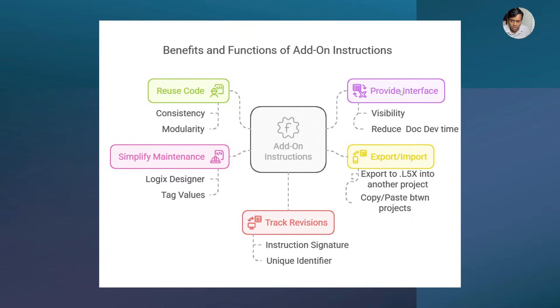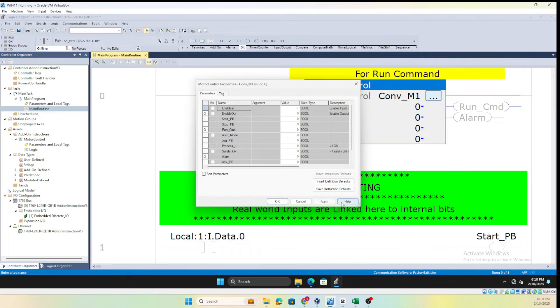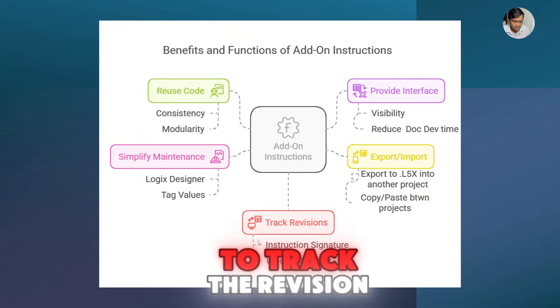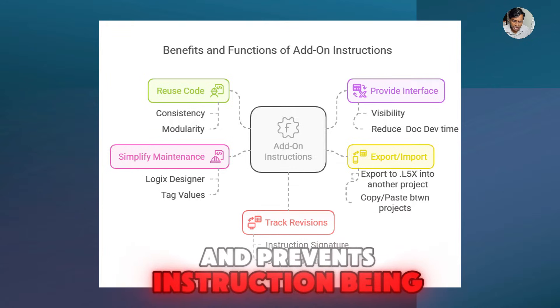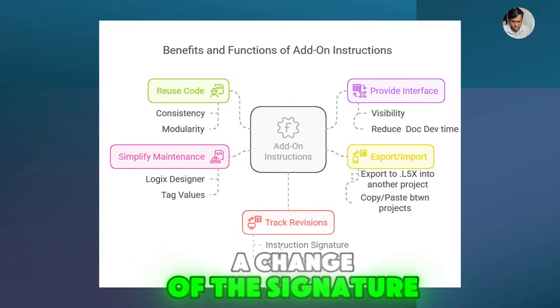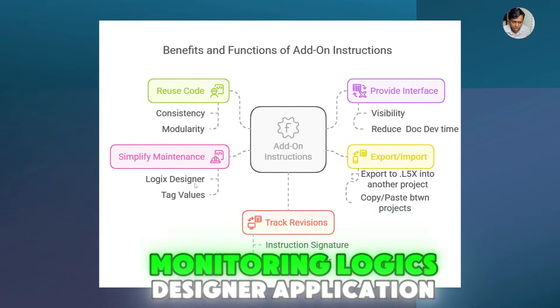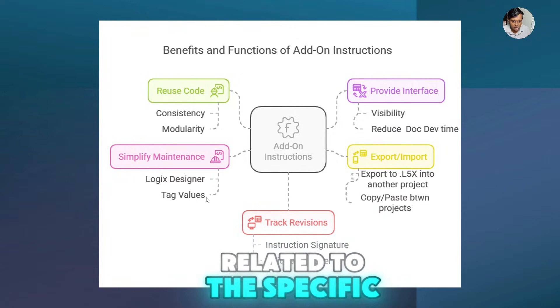Add-on instruction sets also provide an easy-to-use interface just like any other instruction, giving visibility into what's happening and the ability to document how the instruction works. This reduces documentation development time. Another advantage is the ability to import and export into another project using the .L5X extension, or copy-paste between projects. You can also track revisions by adding an instruction signature, which generates a unique identifier and prevents editing without a signature change. Maintenance is also simplified, since add-on instruction sets can be monitored in Logix Designer and will animate tag values for the specific instance.